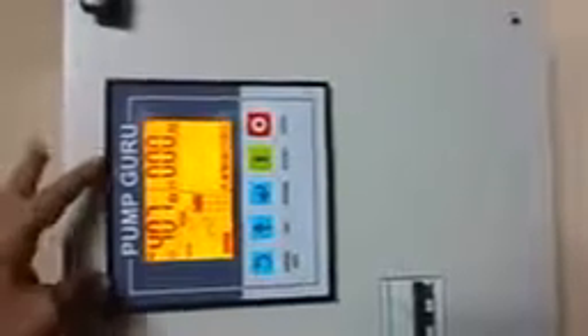The next option is called power. So power is blinking. Now I am setting a power. It is showing the kVA. So this way it stores the last 20 alarms, and you can always see them when repetitive alarms come, so you can take care of those alarms in the condition of voltage or current. If it is tripping all the time with overload, that means you have to find out that there is something wrong with your motor or in the connectivity, where it is taking the higher current. Maybe in the submersible case, there may be a choking in the pipe itself that can cause this kind of problem.